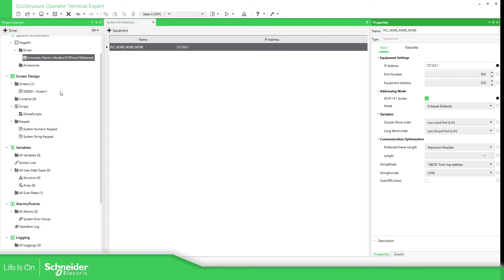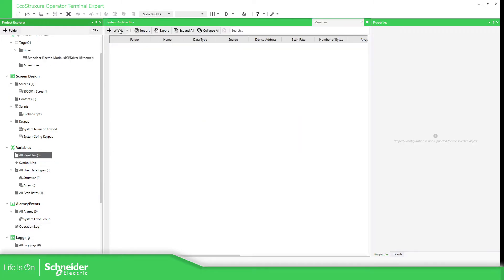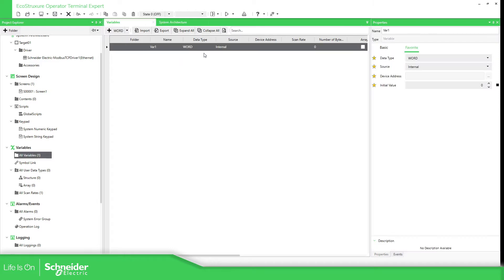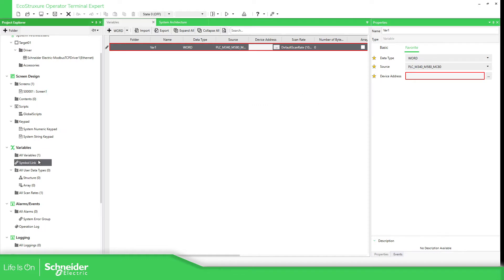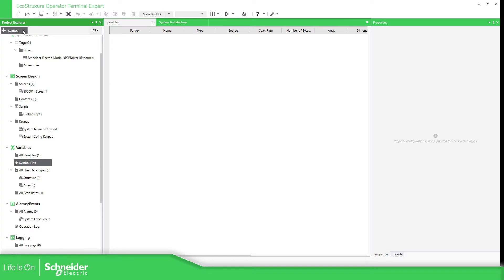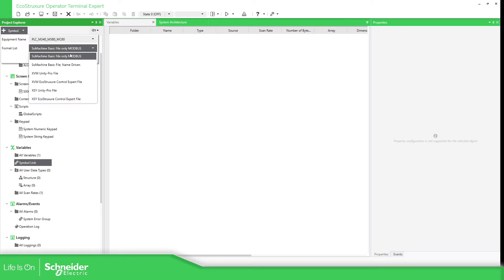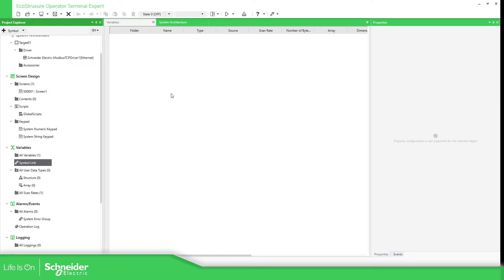Then what we need to do — we have two options. If we know the address of the variable, we just need to add the variable, select the source that we want, and then the device address that we have. Another solution would be to use the symbol link. If we select symbol, we have the possibility to use the XVM — the EcoStruxure Control Expert file. This is the file that we can generate in Control Expert.